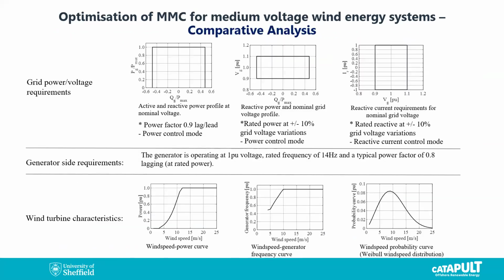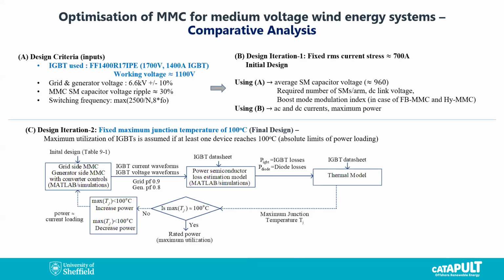The next part will show some comparative analysis that we conducted for the optimized designs of the MMC. We did it with respect to the two-level converter, which is widely available, so we can find some information about it. In this optimized analysis, we considered the grid power and voltage requirements, power control mode, reactive current mode, and wind turbine characteristics, considering wind speed and the probability curve. Okay, next slide.